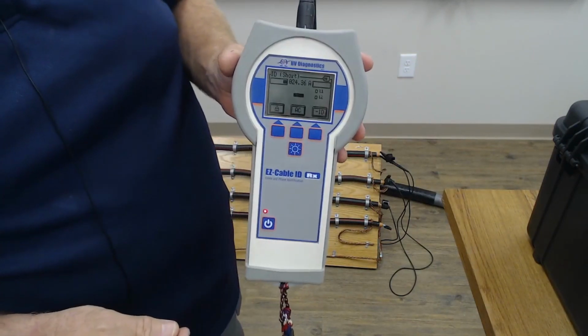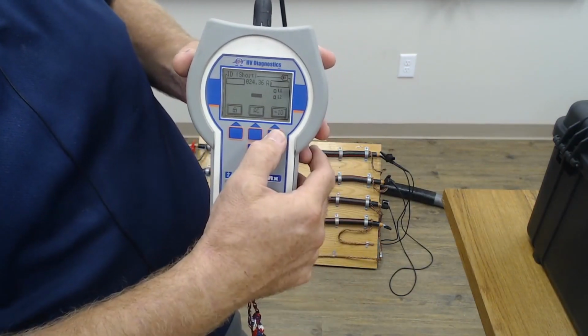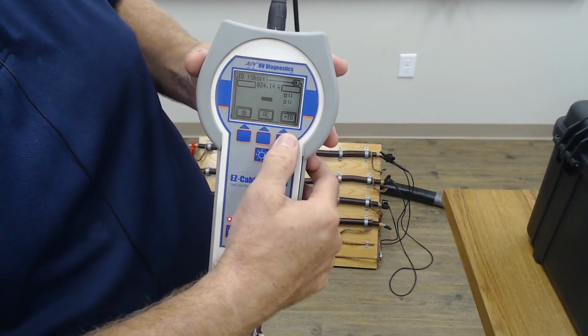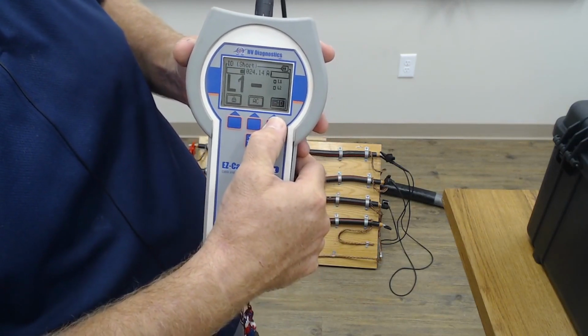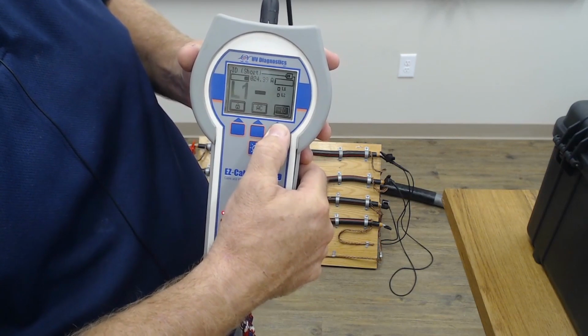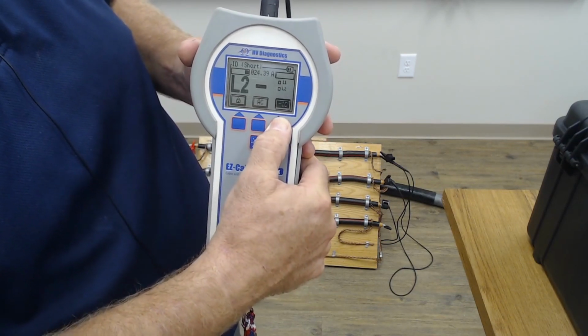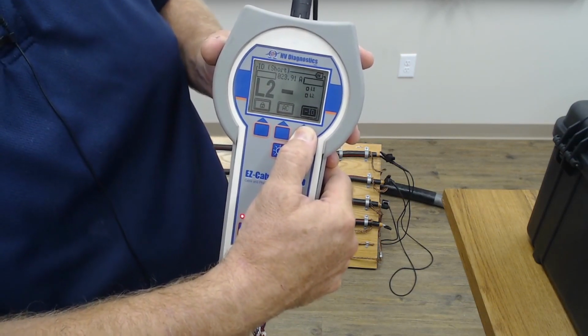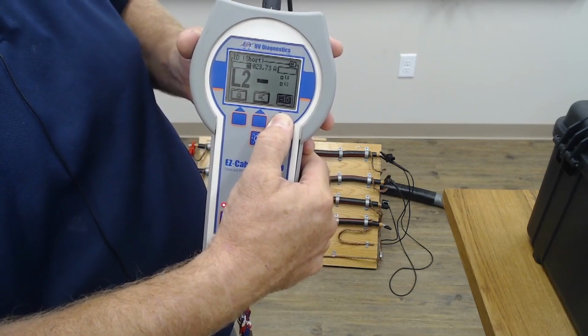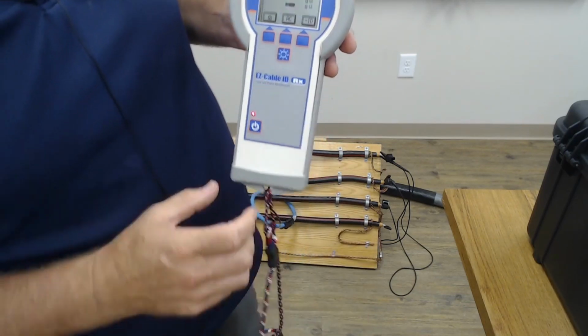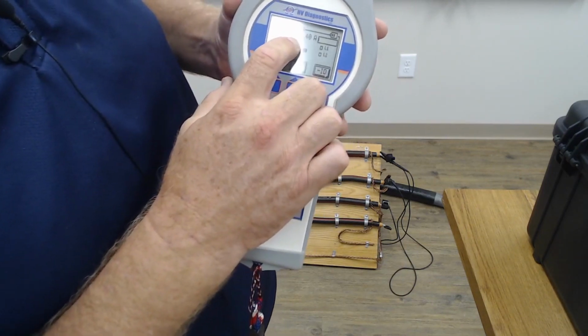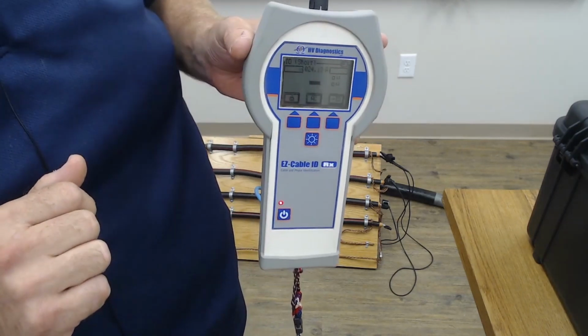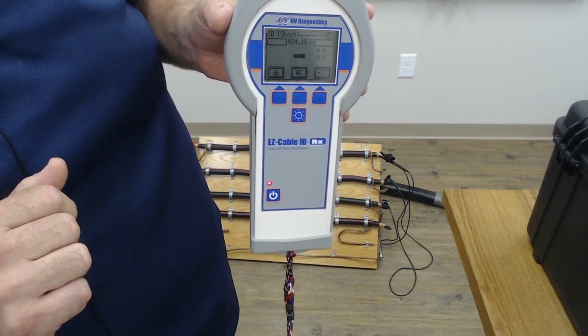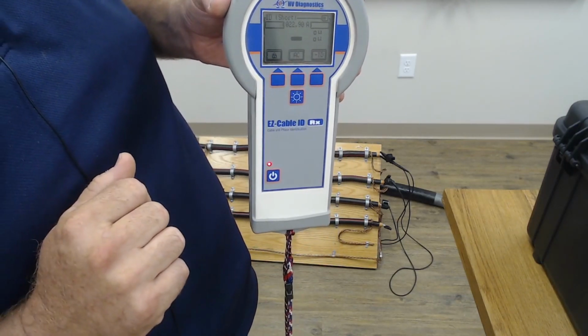And that negative, there we go, that negative should be, if we press this button over here, there should be both L1 and L2 present in that negative. And that's exactly what it should be, and it's completely negative, which is correct. And again, the current should really be around 25 to 30 amps. And if you look over there, we've got about 25 to 30 amps, which is correct.